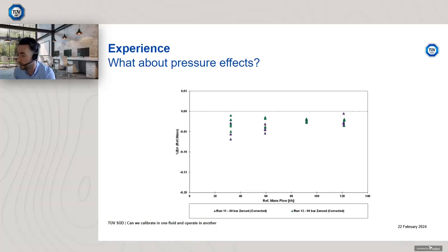We have the 60 bar data, which is purple, and the 90 bar data, which is green triangles. And if you look at the scale of the chart, typically Coriolis meters are 0.1% devices. Remember, the facility uncertainty is 0.08% as well. The vast majority of this data is well within 0.05%. So this shows that a traceable pressure correction can be extrapolated. So if you calibrate even up to say 40-50 bar and you get a nice linear pressure correction value, you can potentially then extrapolate that to 100 bar, 150 bar with confidence.